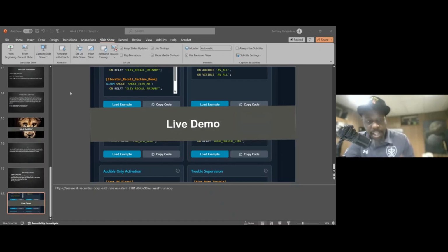So whatever devices are within this AND group need to perform whatever function you identified here. So I need an activation of 3 of them to go into alarm before this AND group will go true. And once 3 of those smoke detectors, let's say under the raised floor, go into alarm, then that AND group will become true.